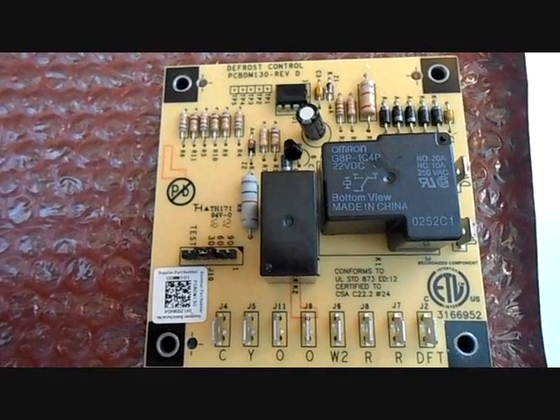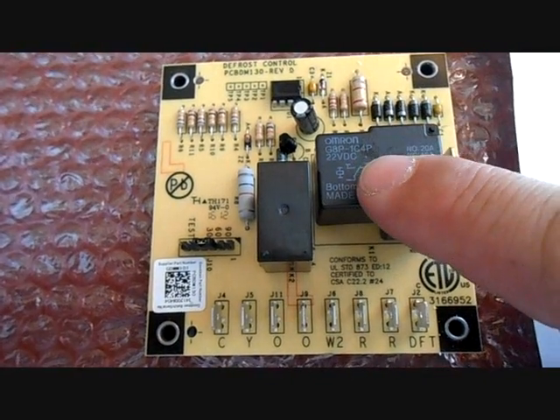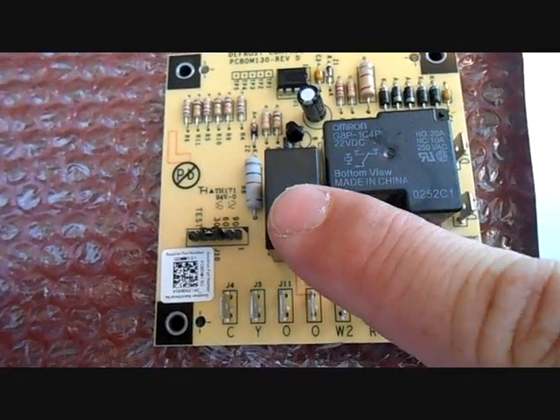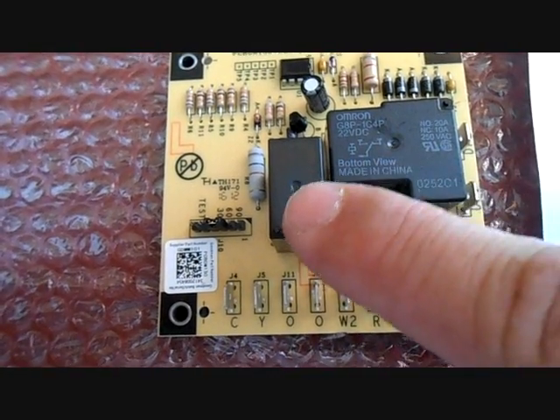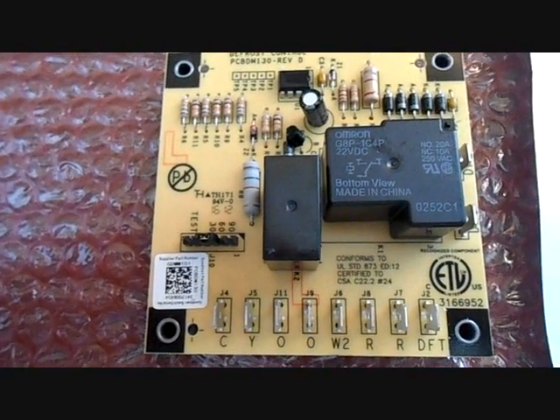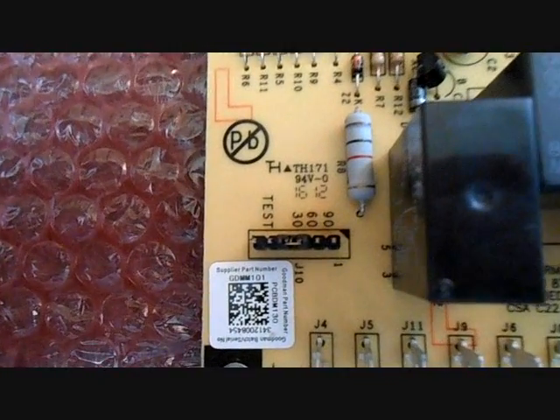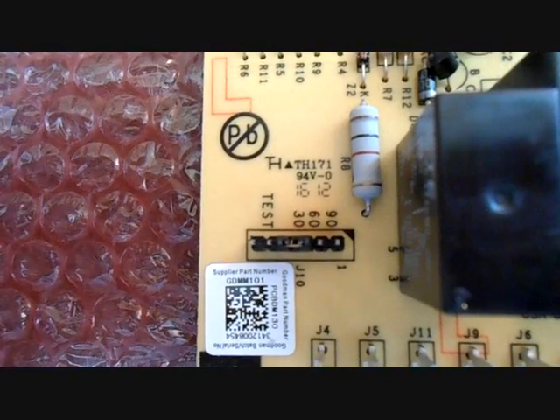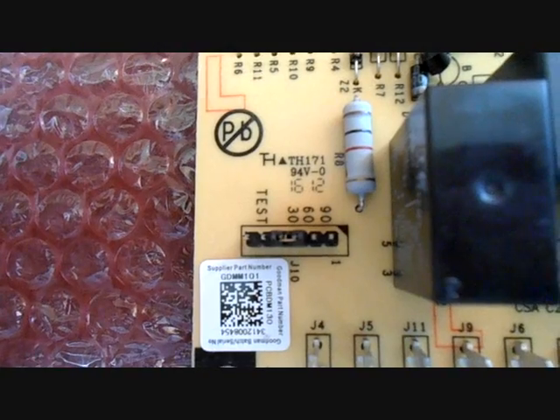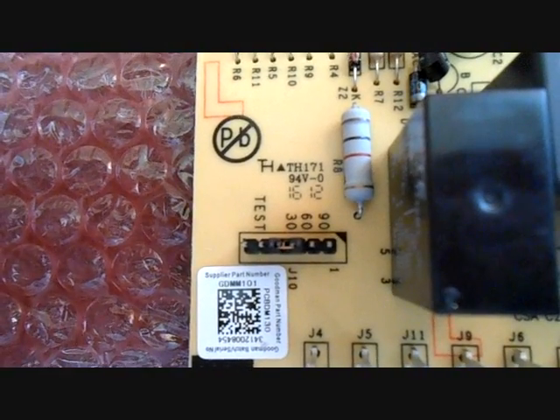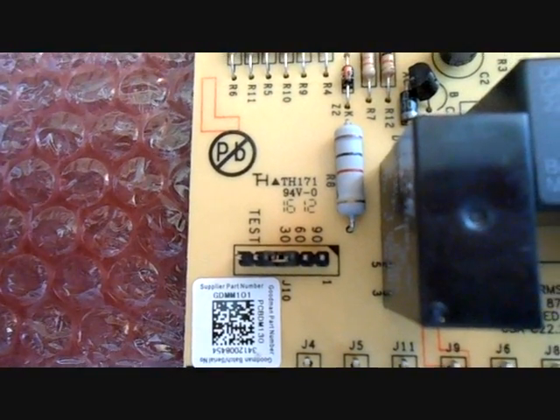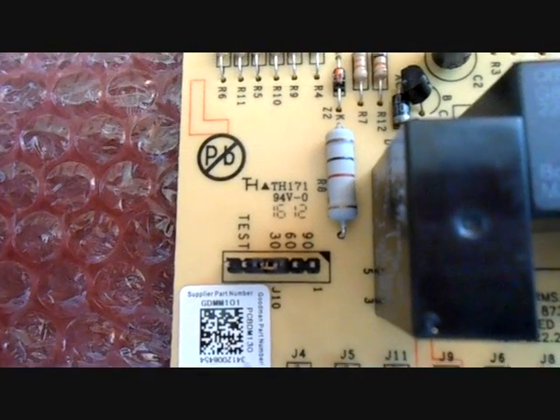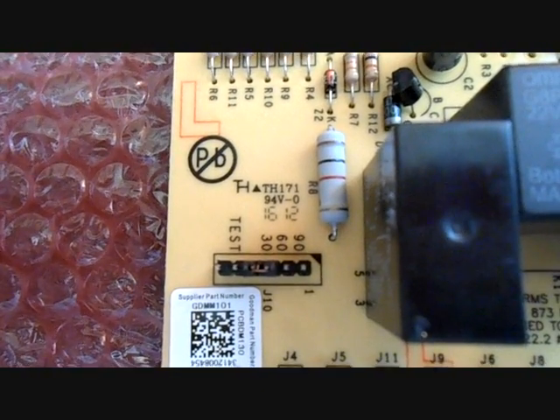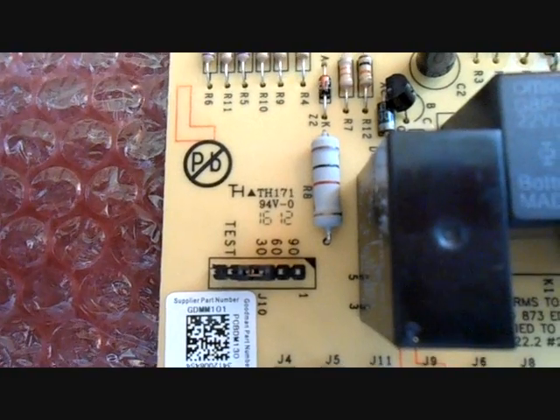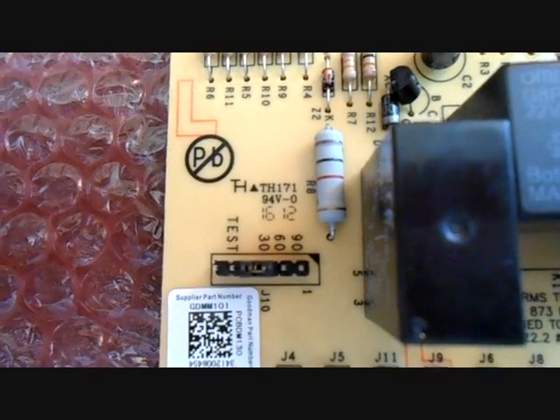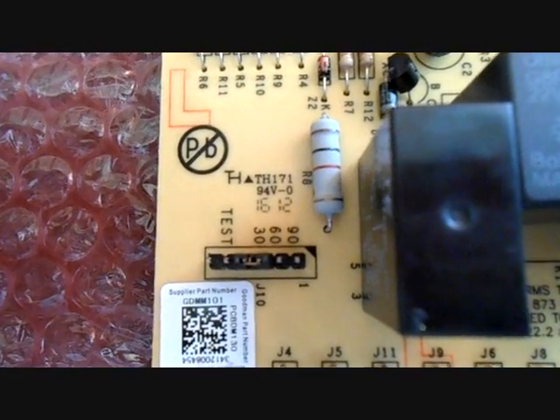As you see, we talked about the two relays and contacts. This is your fan relay on the board. This is the other relay where it sends the power to the reversing valve and the heat strips. What we're going to talk about here is, as you see, there's a 30-60-90 and test. 30-60-90 is your defrost interval, whether you want it to be 30-minute intervals, 60 minutes, or 90. Milder climates will probably choose 90 because it'll be less critical. And if you're a more northerly climate, you'll probably choose 30, so it defrosts more often.